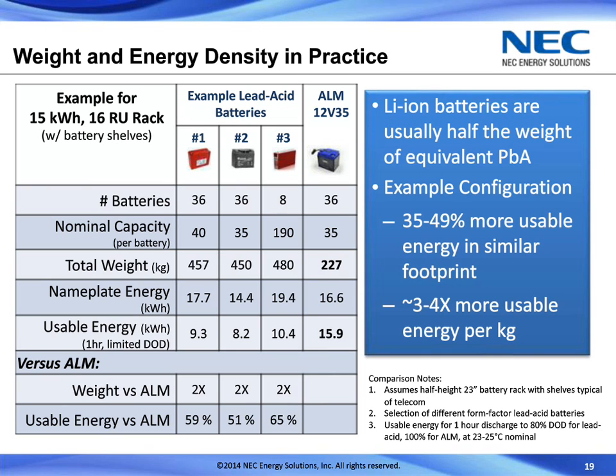And it turns out that once you actually do a little bit of derating for the different applications and look at the number of batteries we need and what the usable energy would be within that space, a lithium-ion can provide up to 50% more usable energy in the same footprint and be half the weight of the other batteries in that environment. So we get far more energy, 3 to 5 times more energy per kilogram, and 50% more energy per unit weight, anywhere between 35 and 50, depending on how we would configure it. So there's a lot that can be done, and this has applications in areas where weight and space are important.